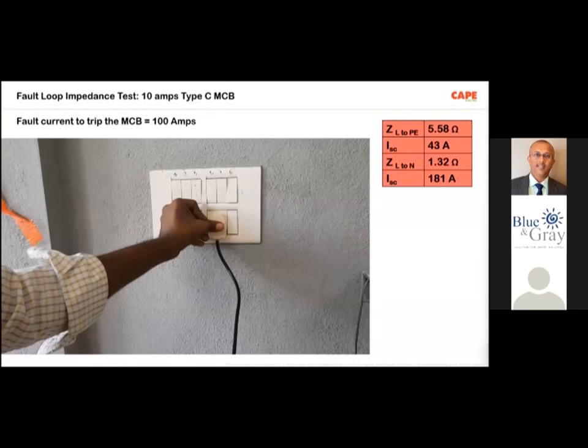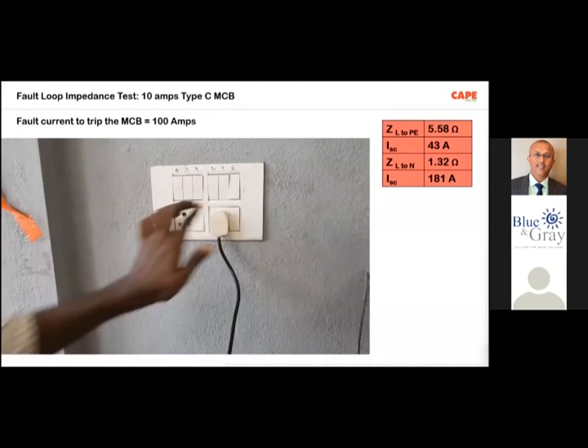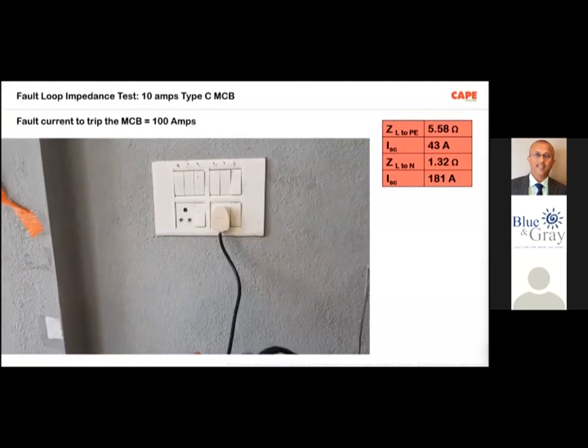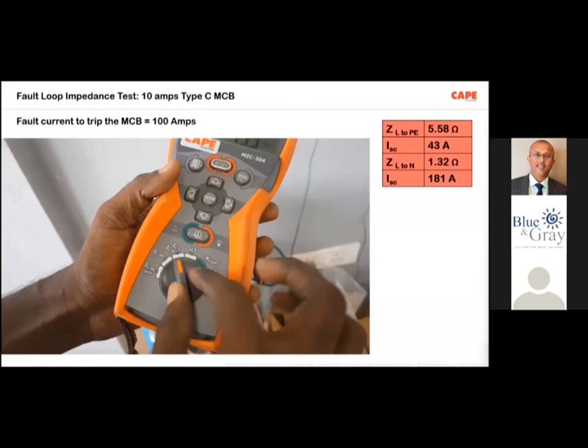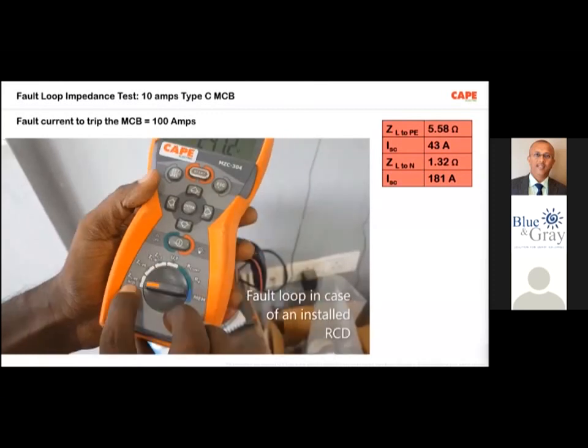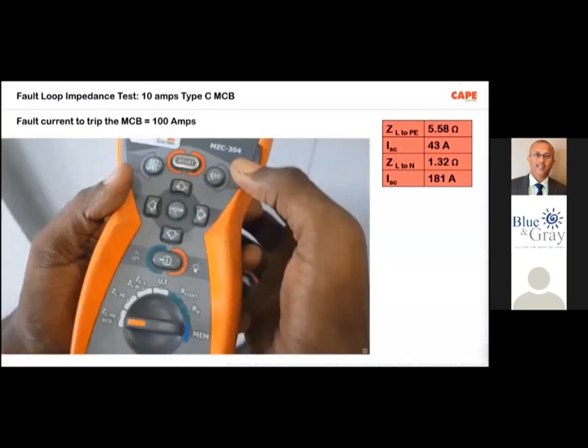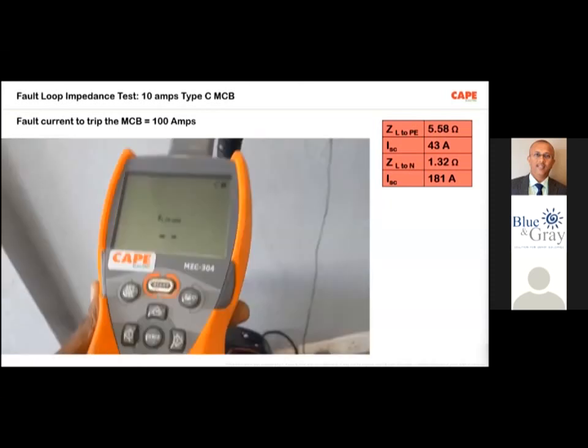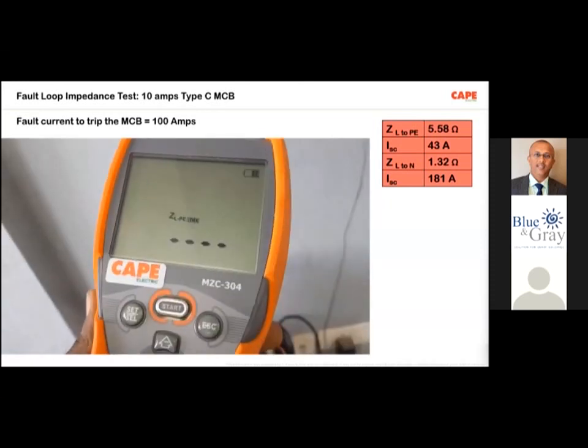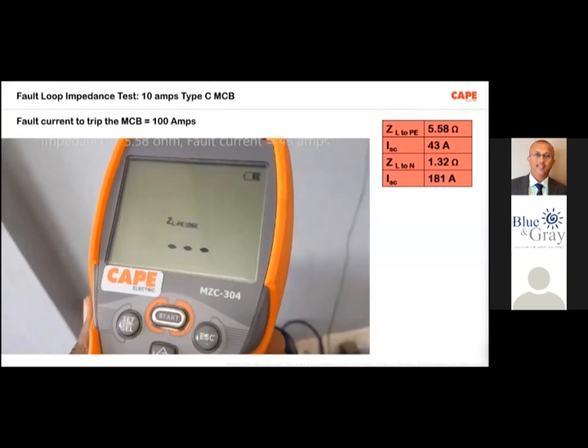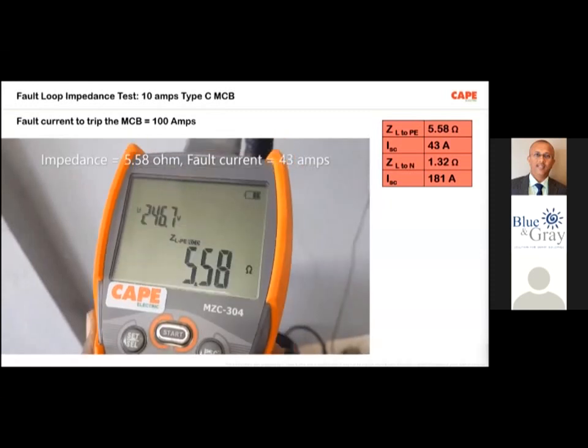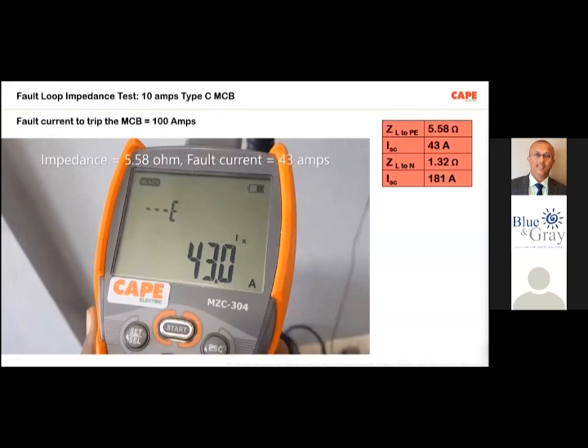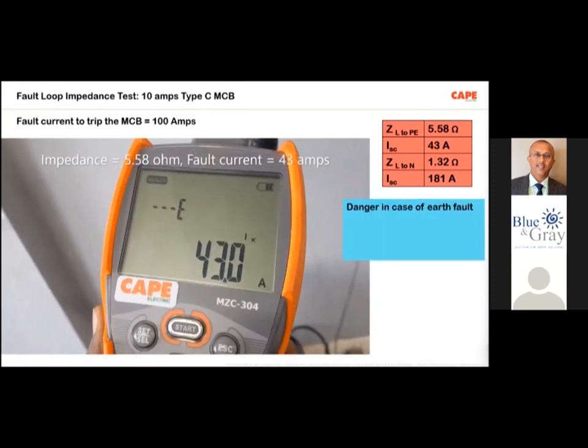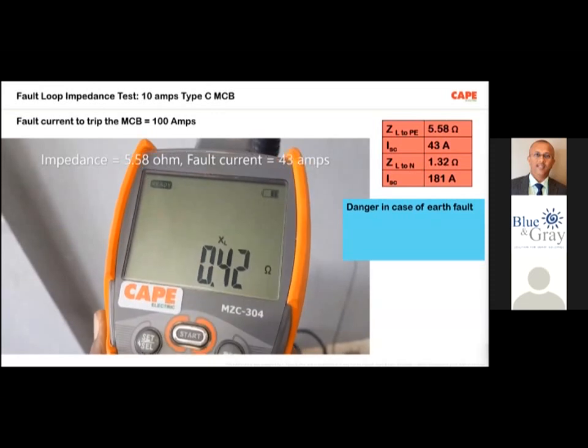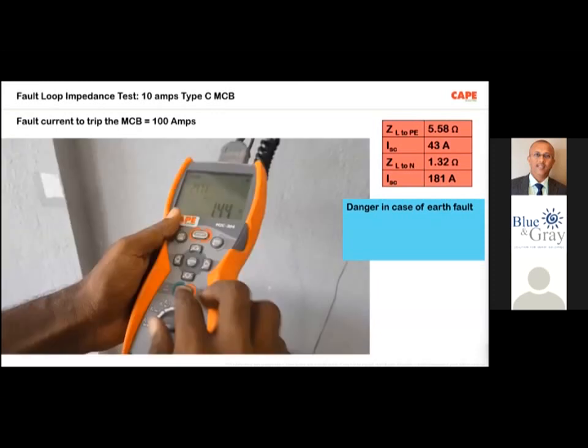Now, in this particular case, the expected current is something about, the video is coming back. The fault loop impedance with this meter, we are getting a value of 5.58 ohm. See, Z L to P, line to P, RCD means this test is for a circuit which has an RCD. We are trying to test the efficiency of the 10 amps MCB. Minimum current is 100 amps because it's a type C MCB. Now we have the fault loop impedance 5.58 and the fault current 43 amps. So it is actually in danger. We require minimum 100 amps to trip the MCB, whereas the current is only 43 amps. So we are technically in danger.